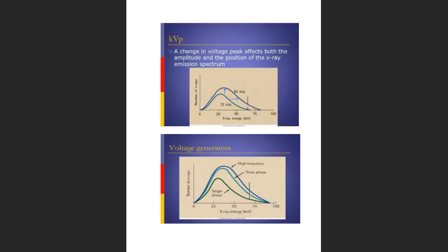Yes. Okay, that's an important thing to recognize with kVp because we're always telling you, when you change kVp, you affect the quantity and the quality of the beam. It's real important to recognize that because we do shift the number of higher energy X-rays. We still are going to have low energy because we're only changing kVp. If we change filtration, then we would have that movement on the front end of the curve versus on the back end of the curve.